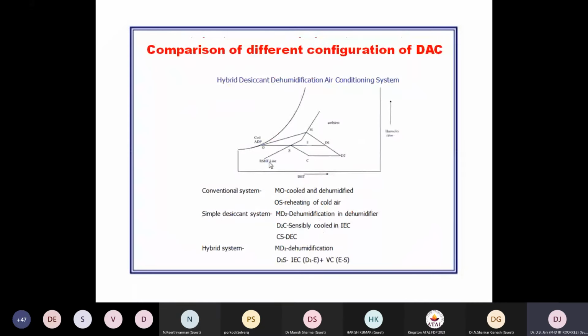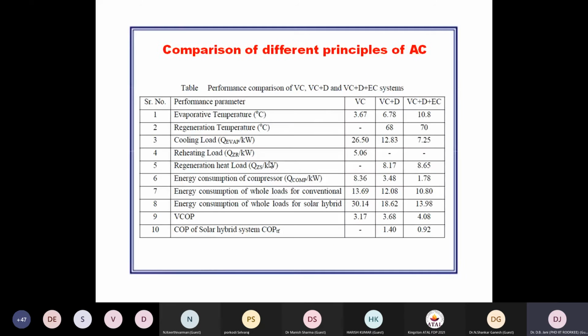So this is how we can compare a combination of different dehumidification and cooling systems on the psychrometric chart. If vapor compression alone is used, you can obtain a COP of 3.17. If we use a combination of desiccant vapor compression hybrid cooling, then the COP improves to a slight extent. If we compare it to the evaporative cooler for some typical applications, the COP for the same system may rise above 4. So this is how we can improve the COP based on the typical configuration.